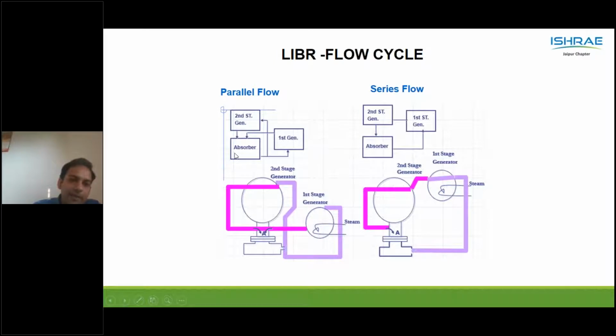lithium bromide. So the flow of lithium bromide is parallel flow and series flow, that is, from the absorber suppose 50% of the lithium bromide, the dilute solution, goes into the second generator and 50% will go into the first generator. They will further concentrate based on their heats and both are combined and sent to the absorber. This happens in the parallel flow design. In series flow, 100% is sent to the first generator.